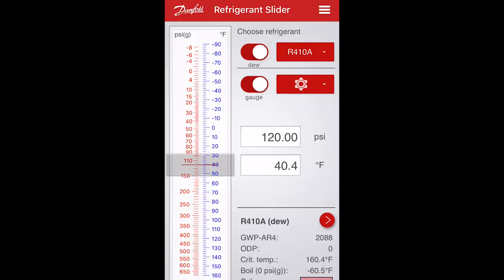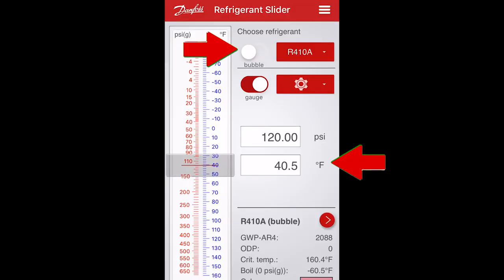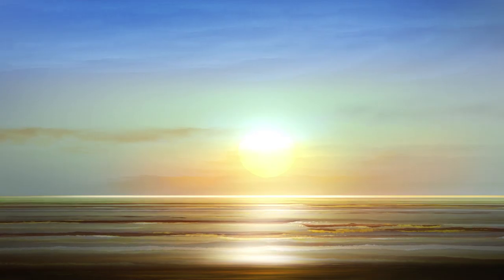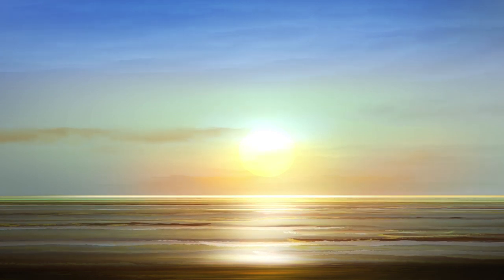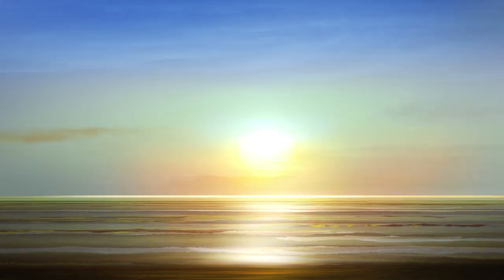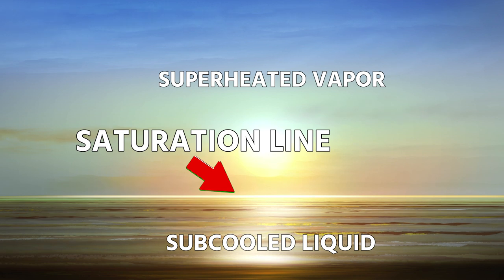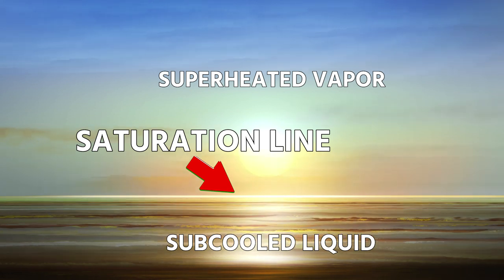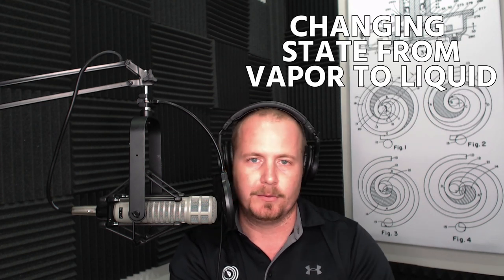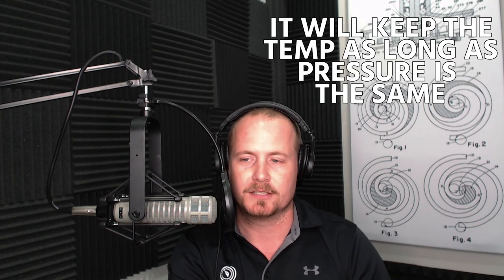You look at something like R410A. If you take a look here, it only has 0.1 degrees of glide at a 40 degree evaporator coil between dew and bubble point. But let's talk about what dew and bubble point are. So imagine that you're looking out on the horizon and you have the ocean down below and you have the sky up above. That thin line would be what we would call the saturation line. And that's the line at which, if the refrigerant is boiling or condensing, changing state between vapor and liquid, it will be at that temperature so long as the pressure is the same.